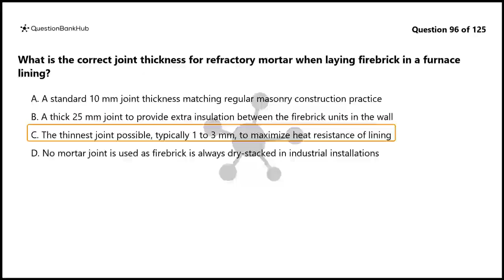A 10 mm joint exposes too much mortar area to heat. A 25 mm joint would fail rapidly. While some applications use dry stacking, most industrial furnace linings require thin mortar joints for gas-tight construction.